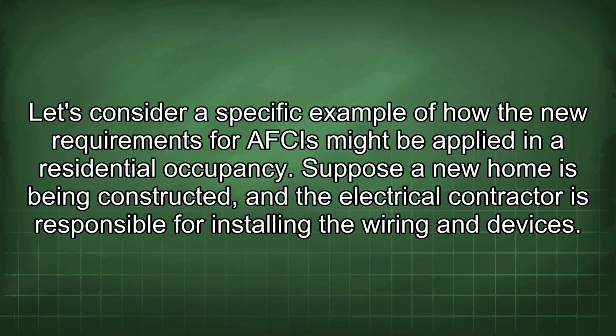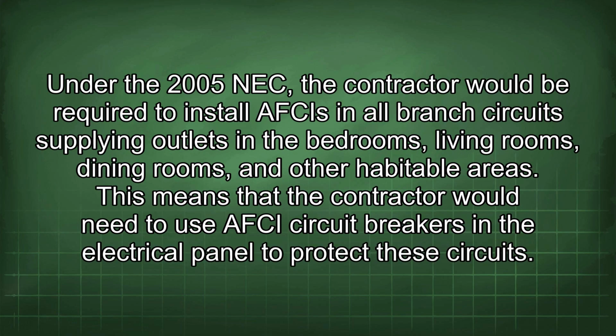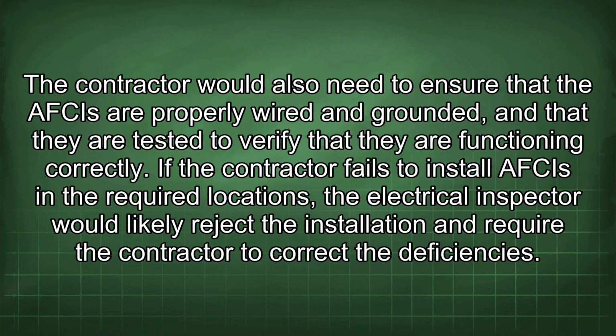Let's consider a specific example of how the new requirements for AFCIs might be applied in a residential occupancy. Suppose a new home is being constructed, and the electrical contractor is responsible for installing the wiring and devices. Under the 2005 NEC, the contractor would be required to install AFCIs in all branch circuit supplying outlets in the bedrooms, living rooms, dining rooms, and other habitable areas. This means that the contractor would need to use AFCIs circuit breakers in the electrical panel to protect these circuits. The contractor would also need to ensure that the AFCIs are properly wired and grounded, and that they are tested to verify that they are functioning correctly.